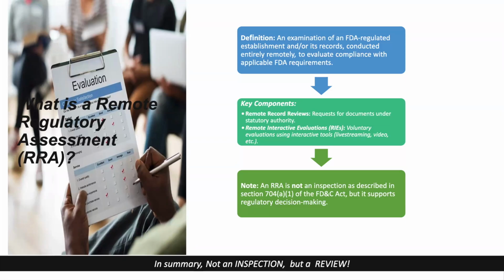So the word compliance here is extremely important, because what that means is that this is serious business to the FDA. And so why is it that the FDA is now getting into these regulatory assessments that are remote? The reason for that is based on a number of factors. One is the volume of work that the FDA has to do. It's immense. The FDA is using a risk-based approach to assessing and monitoring the industry.